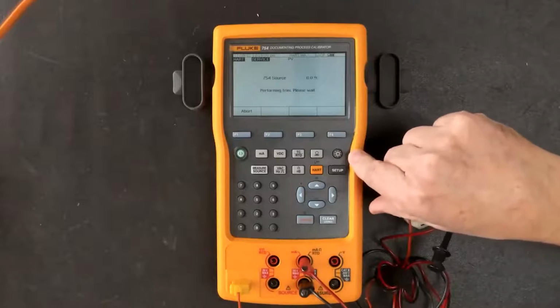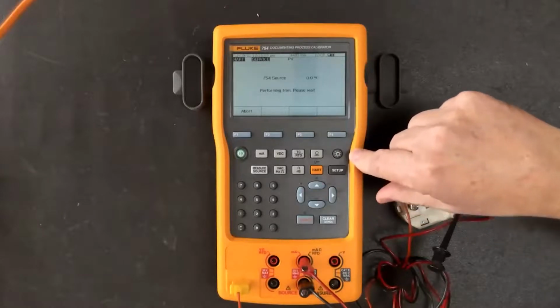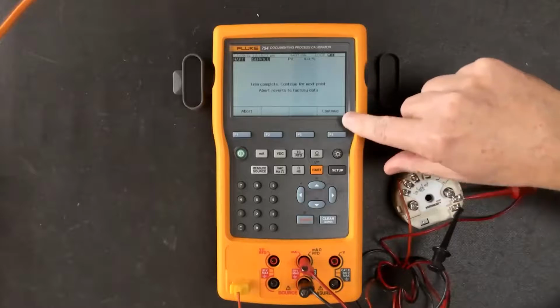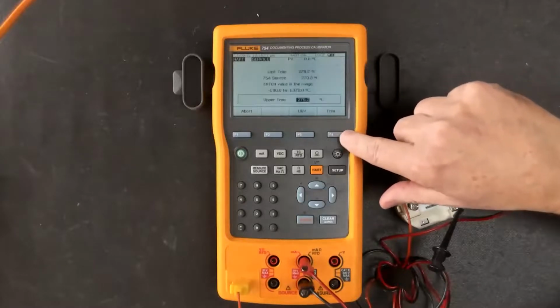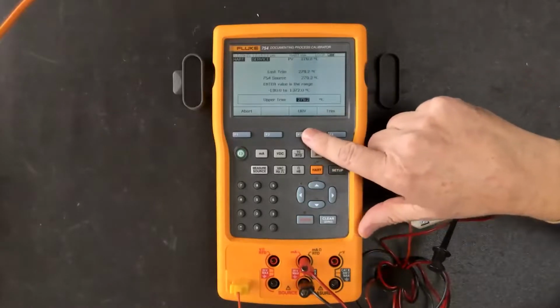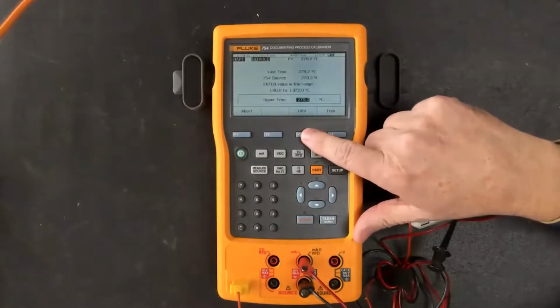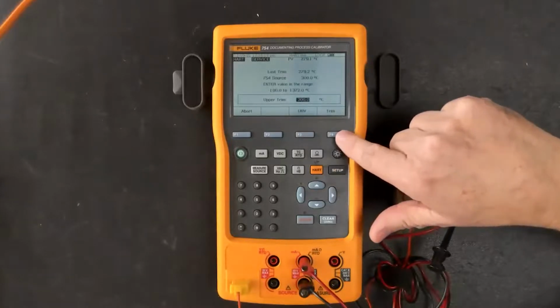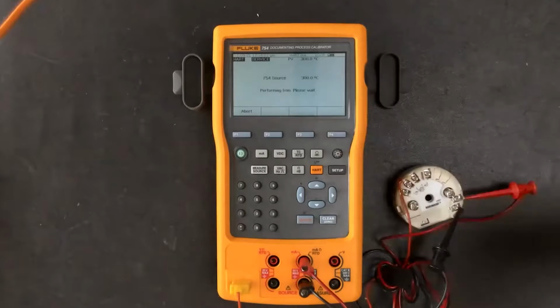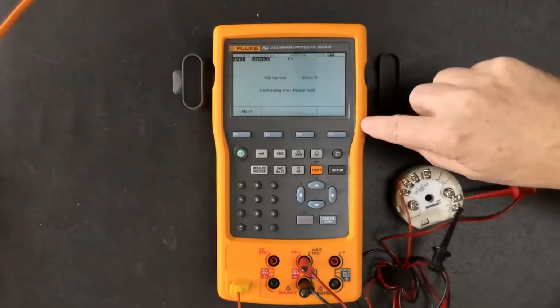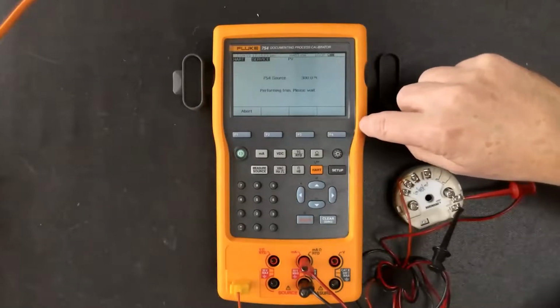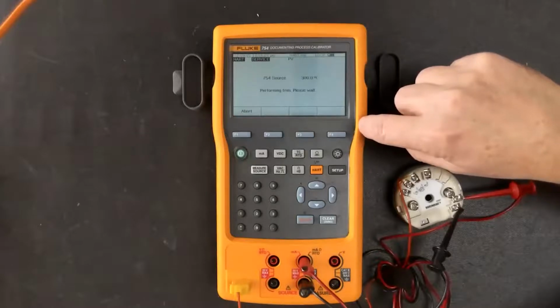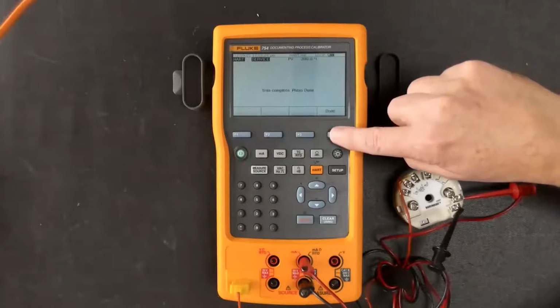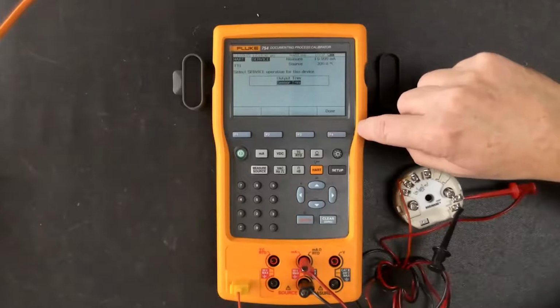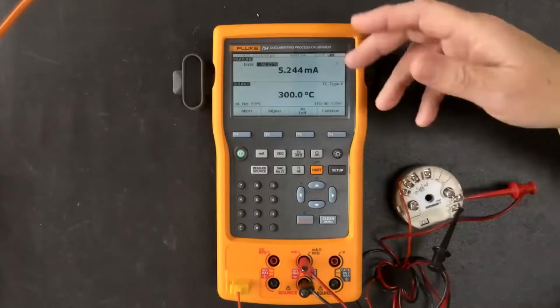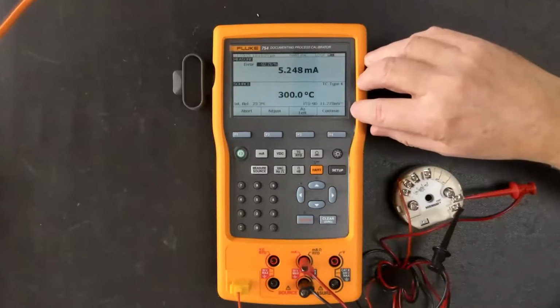And so it's going to set that lower range value to 0 degrees C. Once complete, then we're going to continue and go to the upper range value, which, if you remember, is 300 degrees C. So we're going to set that and trim. And once that is done, we've completed our sensor trim. We've hit the low end, the high end. Okay, and we're done. So now we're back to the main screen.